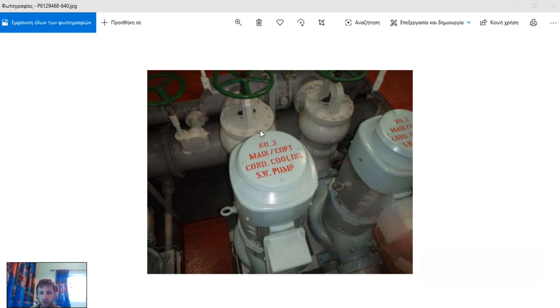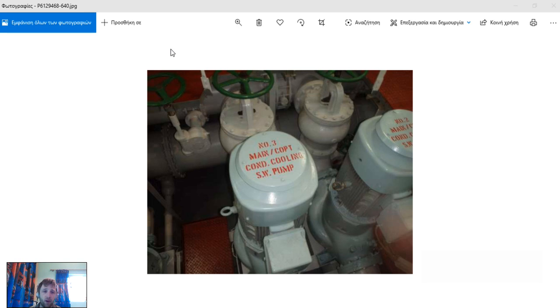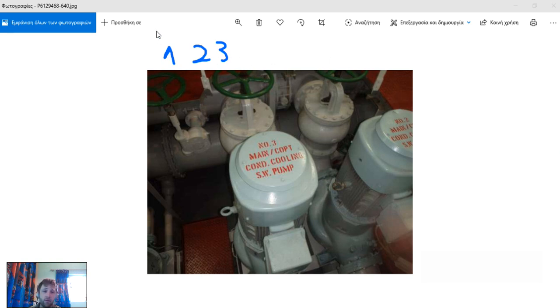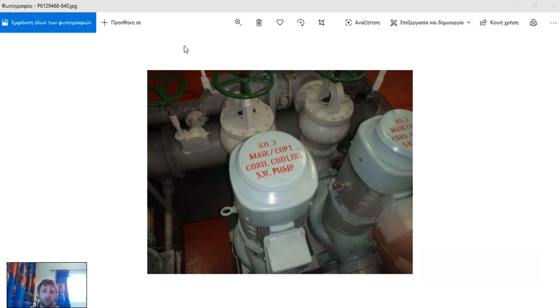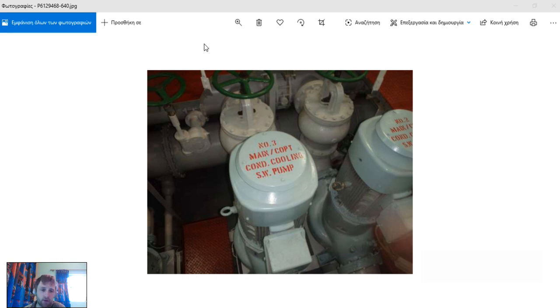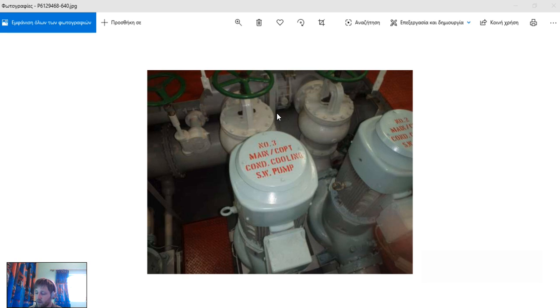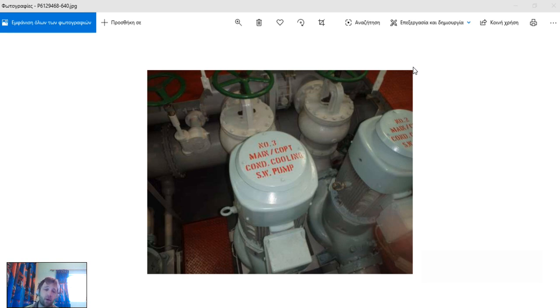Don't forget that all the pumps placed in the engine room - number one, number two, number three, or other pumps between them - must have the same running hours. Let's say this one has 10 running hours, this has 20, and the other has zero. We must set the one with zero to work. We must not have big differences, a thousand hours between the pumps. This shows that all pumps are working equally and changed. Always keep this in mind because I have seen some really big and tremendous differences with the pumps.